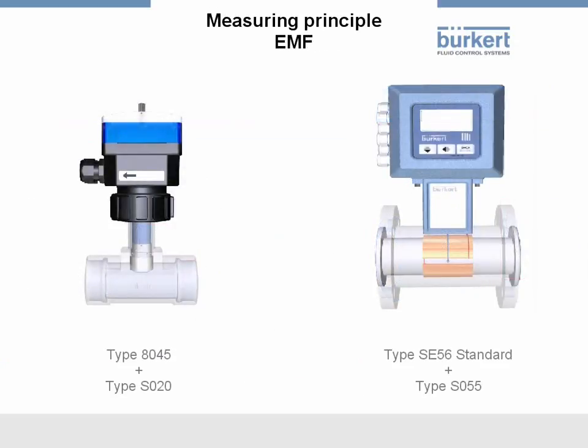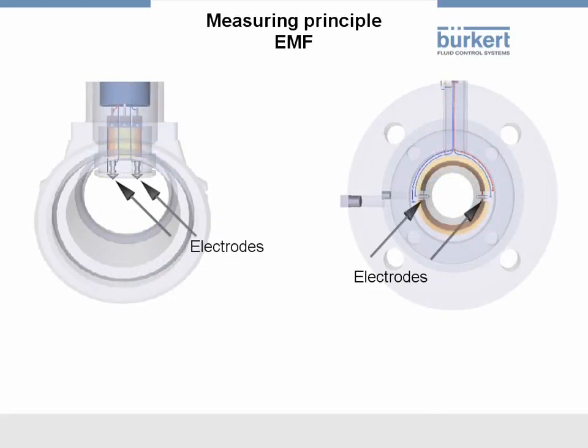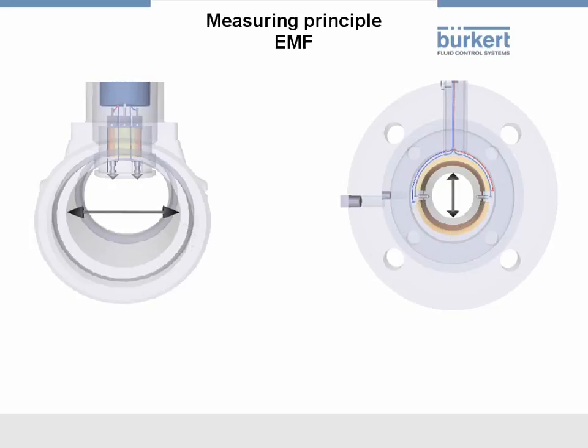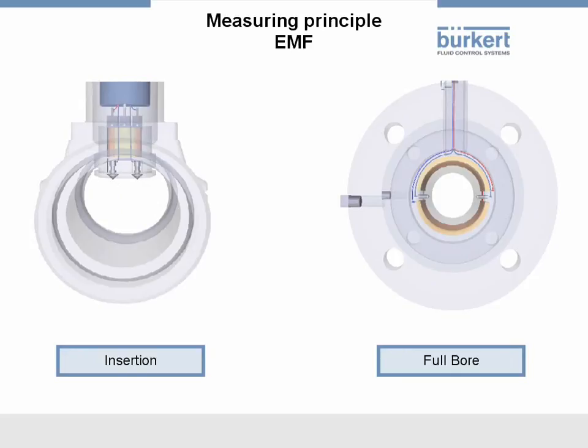But how does this measuring method work? Current-carrying coils generate a magnetic field through which a conductive fluid flows. The voltage induced in the fluid is tapped at two electrodes. The measured voltage is a measure for the flow speed of the fluid. The flow rate is then calculated by means of the inner pipe diameter. This basic principle is identical for the insertion and full-bore versions. Only the positioning of the coils and electrodes is different.